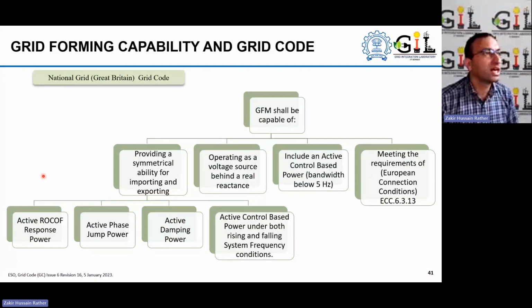So ESO already has grid code regulations, and these are some of the requirements for grid forming technology. It should provide symmetrical ability for exchange of power with respect to active ROCOF response of the power. Phase jump is another additional aspect with grid forming technology, which is not there as such in grid following. It is something that needs to be critically considered and factored in. Damping power is also a requirement, because as I mentioned earlier, there is a capability of damping oscillations in the system. So for grid forming technology, there can be a grid code requirement for demonstrating the capability of active damping power.